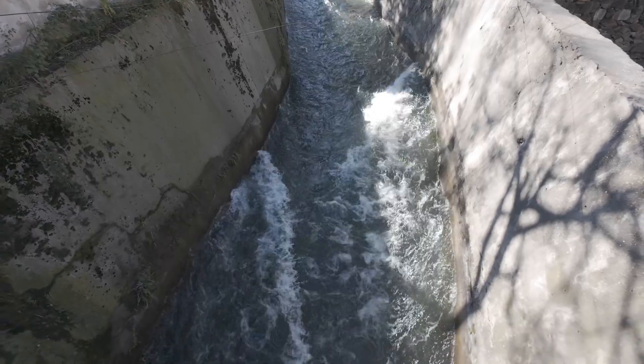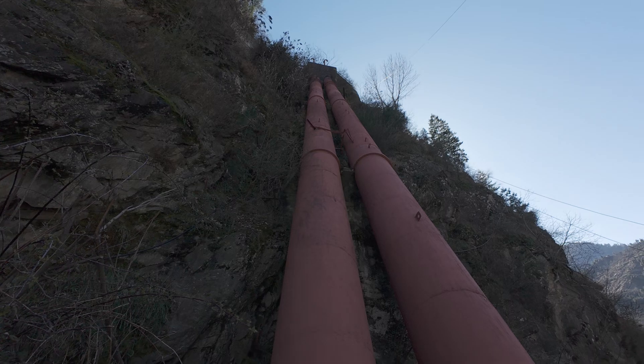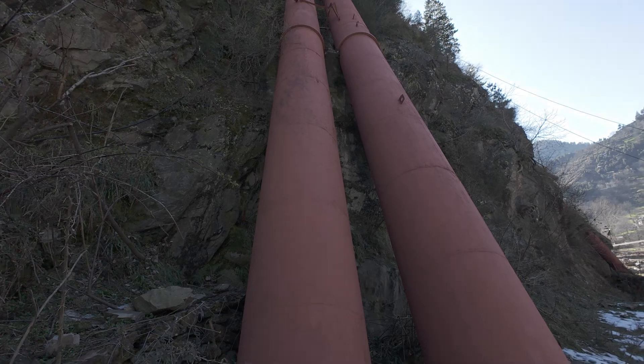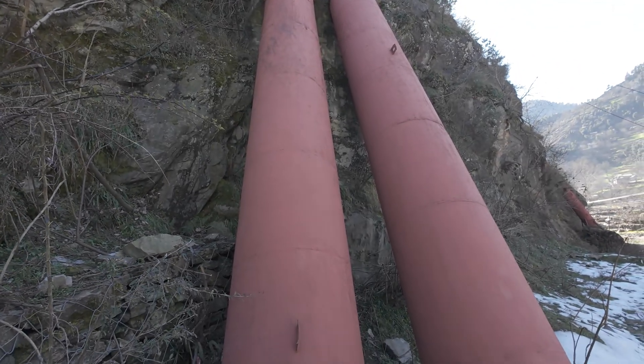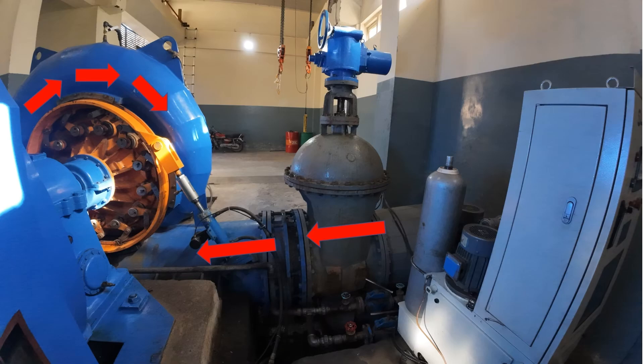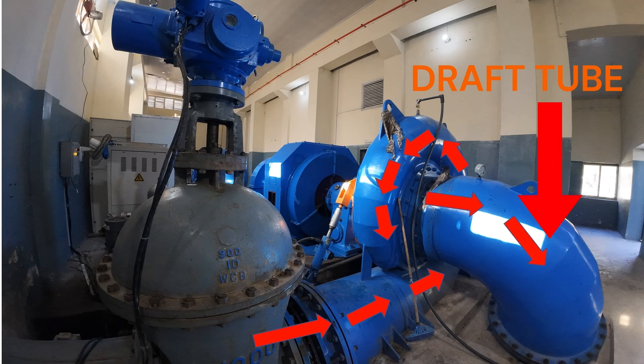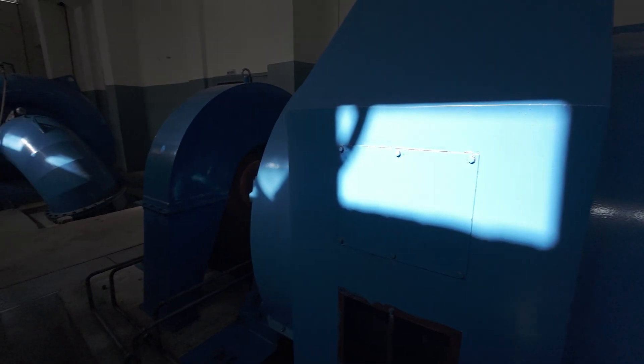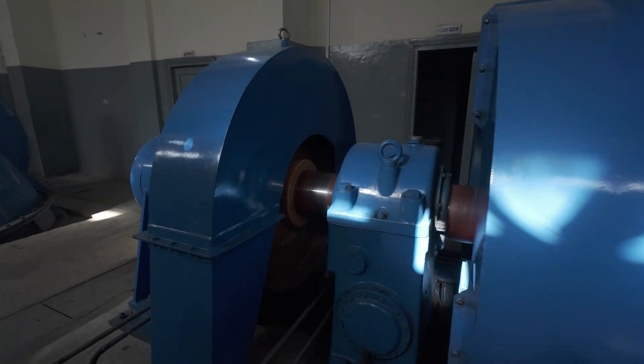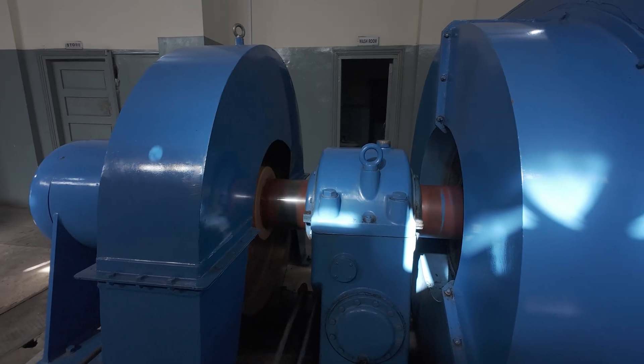So how does it all come together? The river's flow is diverted into a channel or pipe, rushing toward the turbines with just the right amount of pressure. With a flow rate of 2.94 cubic meters per second and a 42.67 meter head, the water spins those Francis runners like a perfectly choreographed dance. The turbines convert that kinetic energy into electricity through a generator excited by a system running at 50 volts and 255 amps.